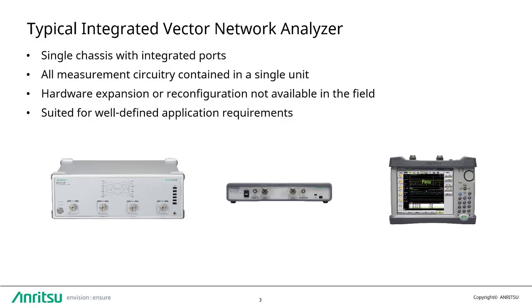A single chassis integrated architecture limits the hardware expansion capabilities of the VNA in the field, so adding ports or extending frequency coverage for future applications is not possible.